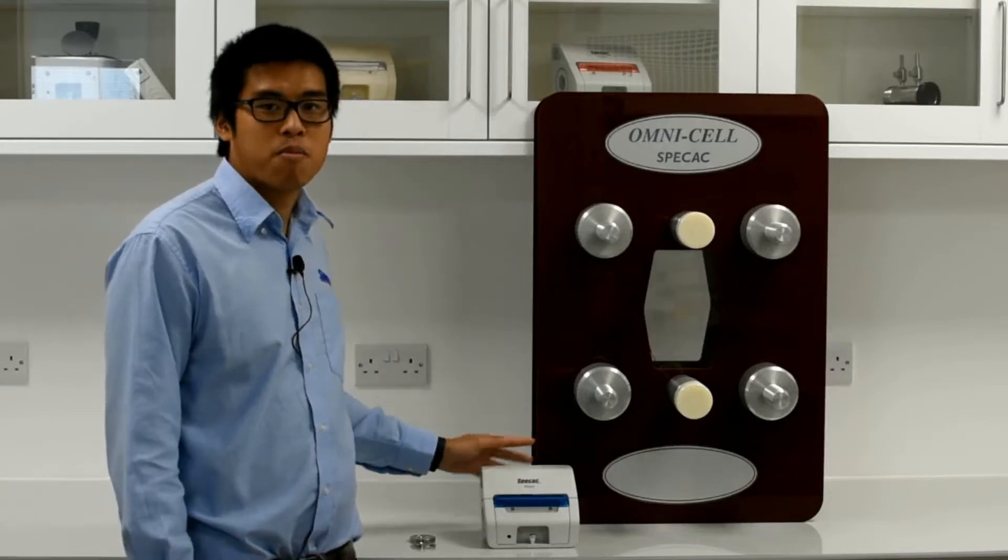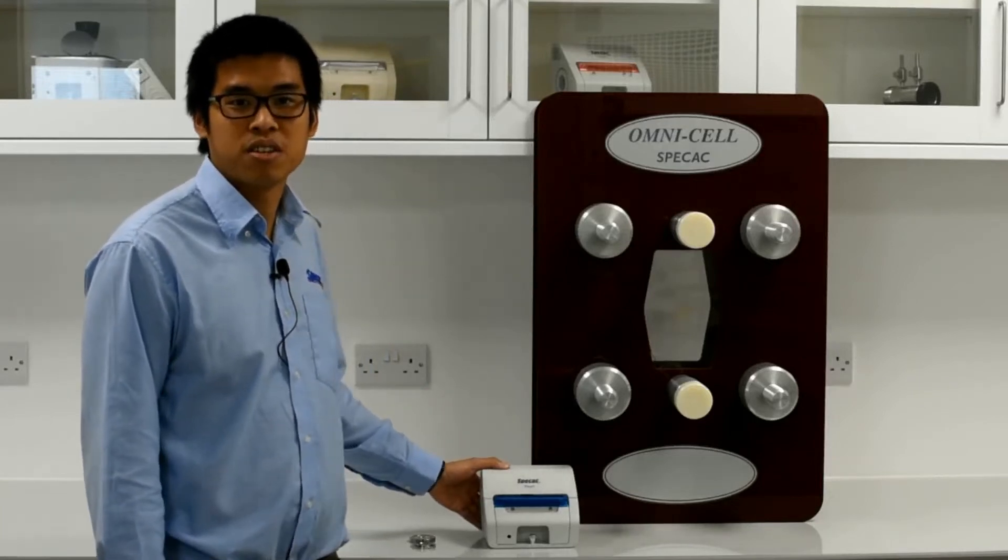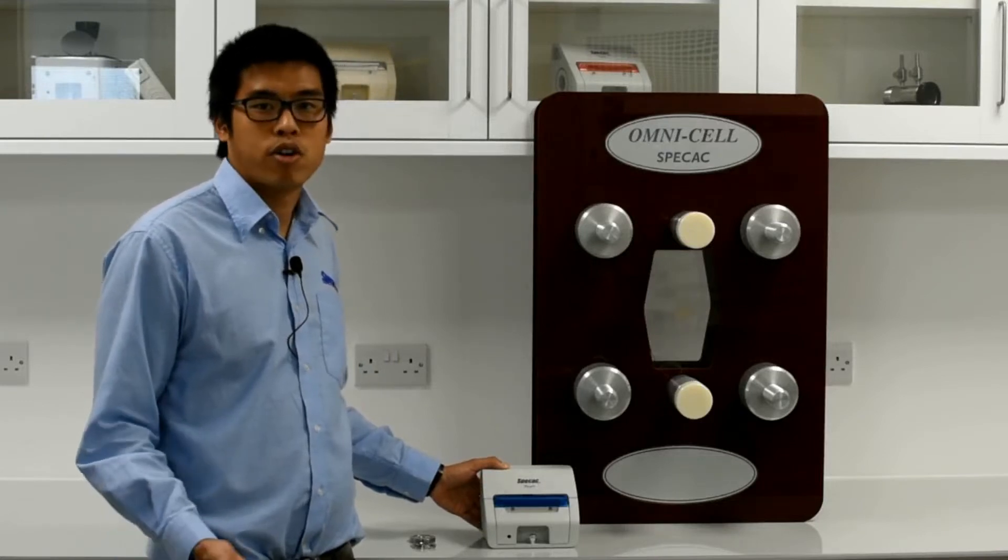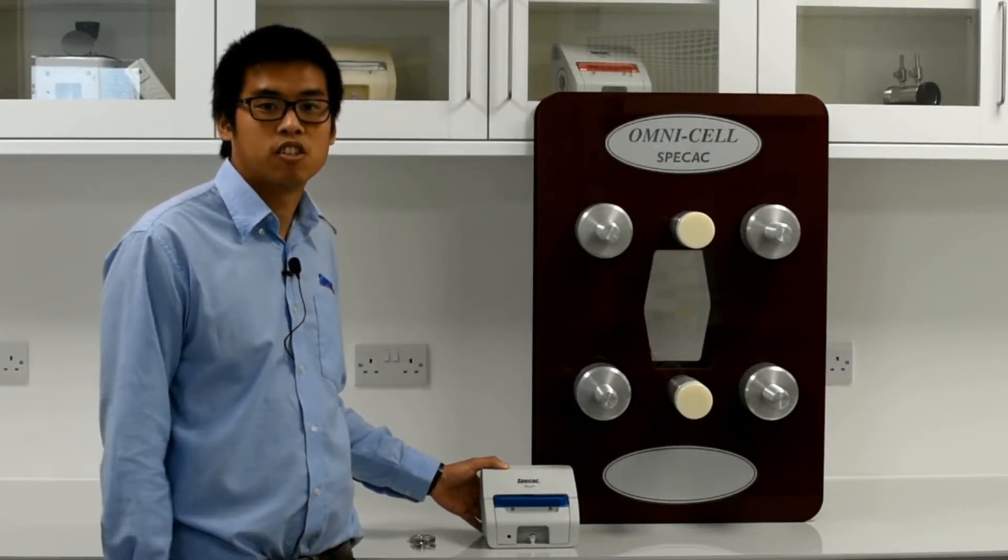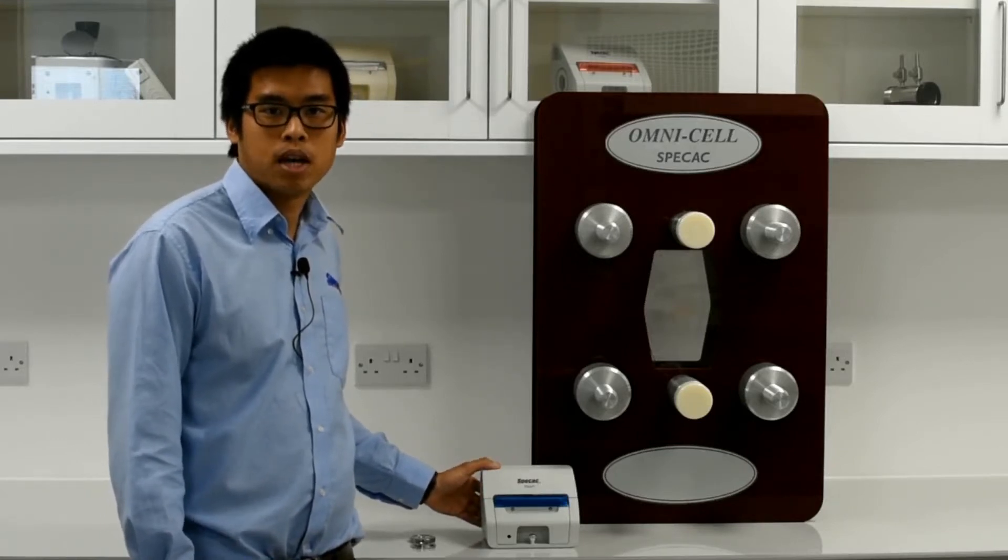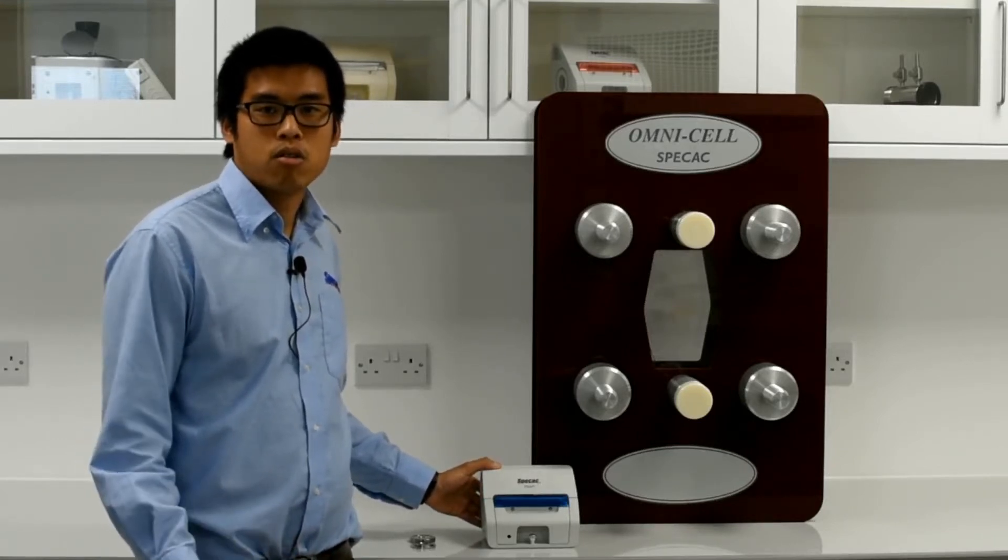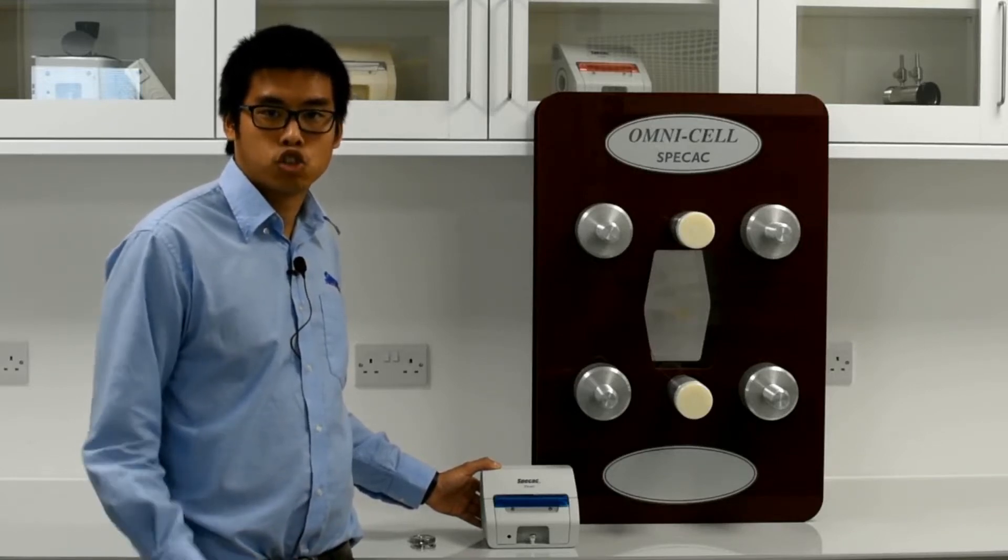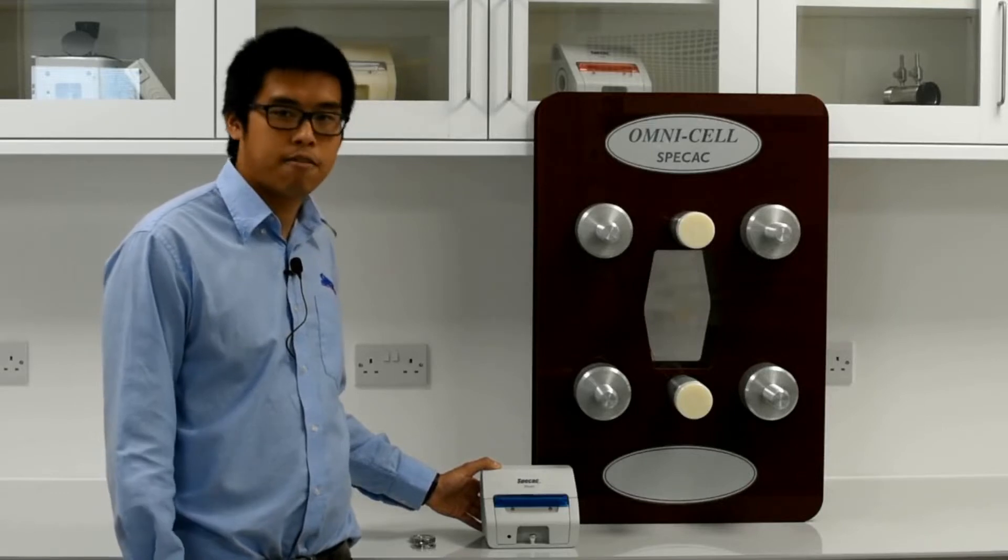Today I'll be talking about one of my favorite accessories, the Pearl liquid transmission accessory. Owing to the transmission technique, which tends to be higher in sensitivity, the Pearl allows the user to obtain spectra of very good signal-to-noise ratio and strong intensity in their FTIR spectra.